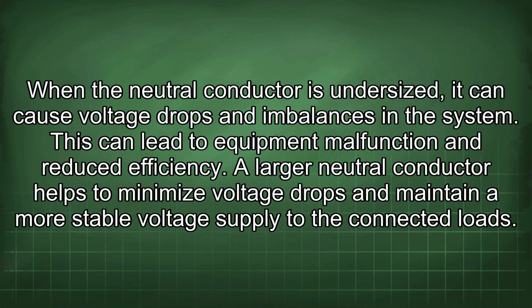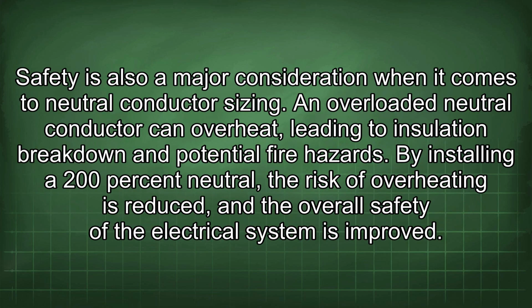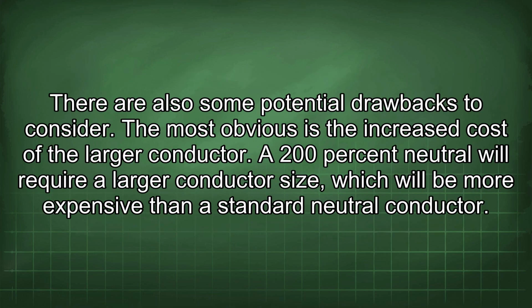When the neutral conductor is undersized, it can cause voltage drops and imbalances in the system. This can lead to equipment malfunction and reduced efficiency. A larger neutral conductor helps to minimize voltage drops and maintain a more stable voltage supply to the connected loads. Safety is also a major consideration when it comes to neutral conductor sizing. An overloaded neutral conductor can overheat, leading to insulation breakdown and potential fire hazards. By installing a 200% neutral, the risk of overheating is reduced, and the overall safety of the electrical system is improved. There are also some potential drawbacks to consider.